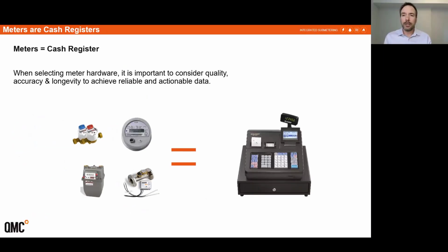When we start looking into building new metering systems or working with existing systems, one of the first things we need to remember is that meters are cash registers. That's the foundation of why a meter exists, and in 95% of meters across North America, why they're there. They're there to facilitate the transfer of ownership between a utility selling electricity, gas, or water to the building or an end tenant, so proper exchange of compensation for that utility can occur.